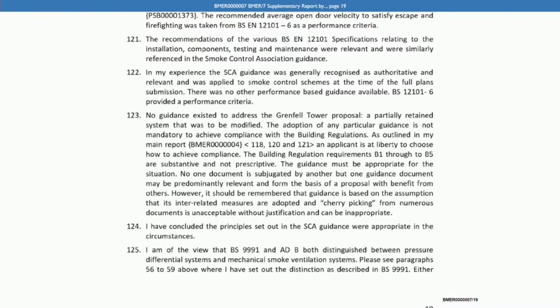Moving on to a new topic now, the Smoke Control Association guidance. Paragraphs 121 and 122 of your report, on page 19, you explain that the recommendations of the various BS EN 12101 specifications relating to installation, components, testing and maintenance were relevant and were similarly referenced in the Smoke Control Association guidance. You say, in my experience, the SCA guidance was generally recognised as authoritative and relevant and was applied to smoke control schemes at the time of the full plan submissions. There was no other performance-based guidance available, and BS 12101-6 provided a performance criteria.